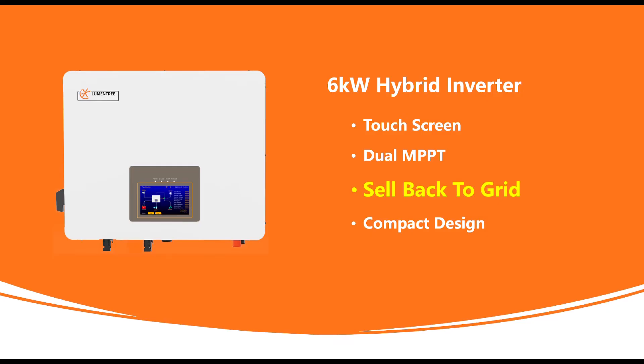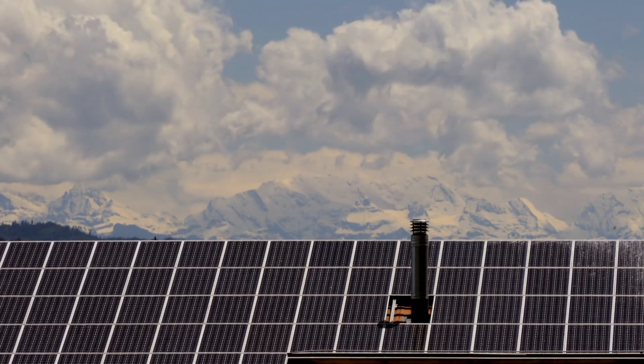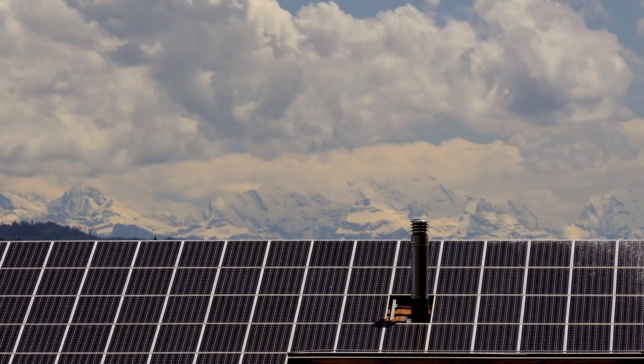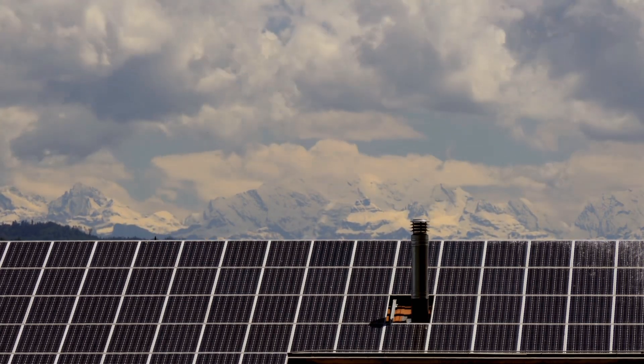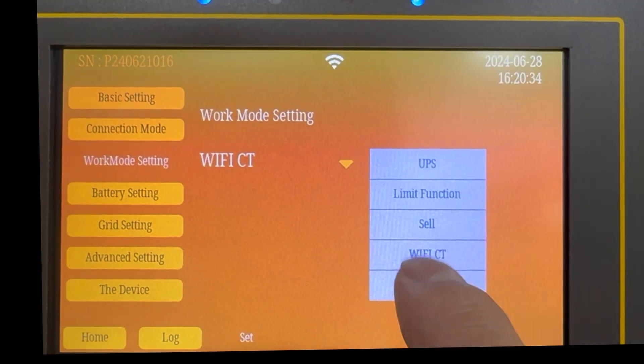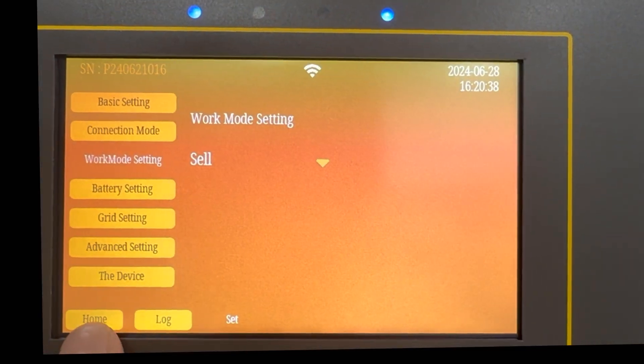The third feature is that the six kilowatt version now has the ability to sell back to grid. This is especially useful when you generate more power than your load consumption and have leftover solar power when your battery is fully charged. All you need to do is click 'Set' on the home page of the LCD screen, find 'Work Mode Settings' on the left column, and select 'Sell'.